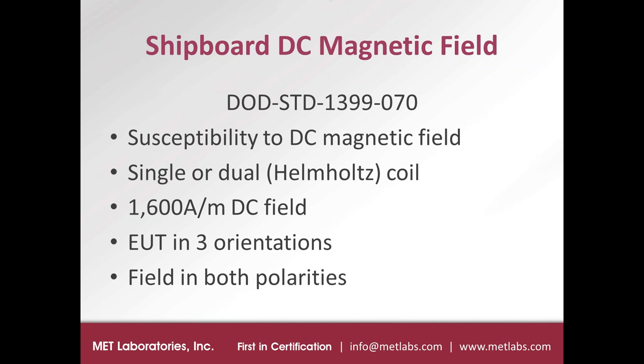And the final test method that I'm going to talk about today is shipboard DC magnetic field. This is another test method that has its own standard that just covers this one test method, which is DOD standard 1399-070. This standard describes a test used to test the susceptibility of subsystems to DC magnetic fields that are generated by the ship. This test can be done with a single or a dual coil. The dual coil configuration is referred to as a Helmholtz coil. And the test level is 1,600 amps per meter DC. The test is performed by placing the EUT in three different orientations relative to the DC field, and then the field is generated in both positive and negative polarity at each of the three orientations.